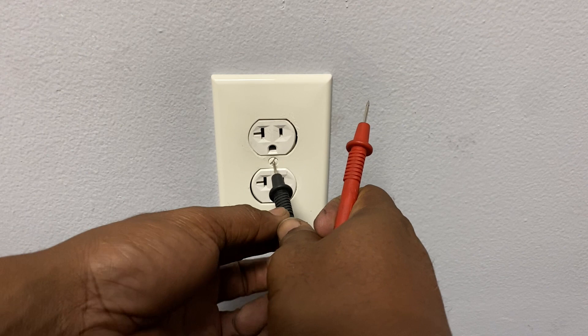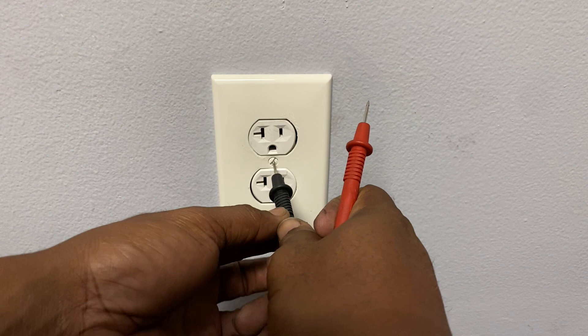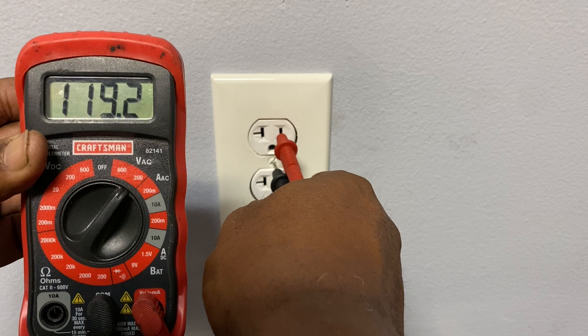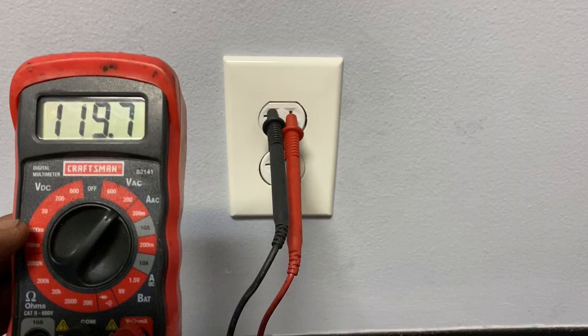Another way to test for a proper ground path is to put the black probe on the ground screw on the socket, then place the red in the hot slot. If you get about 120 volts, then you have a good ground path.